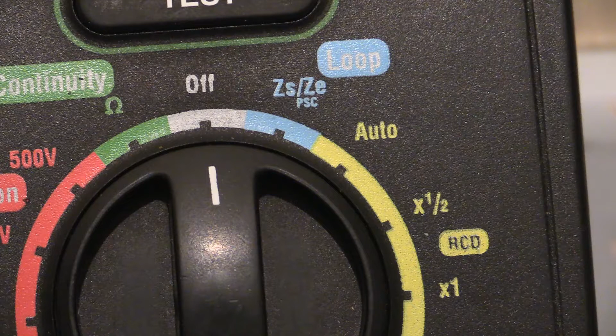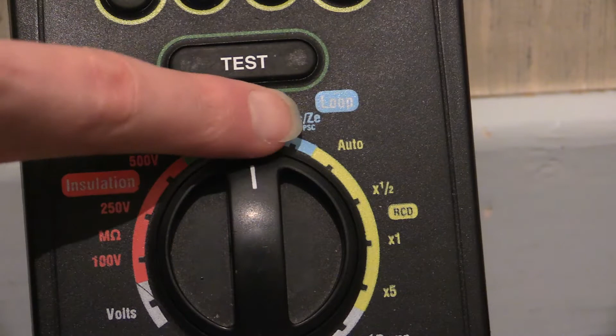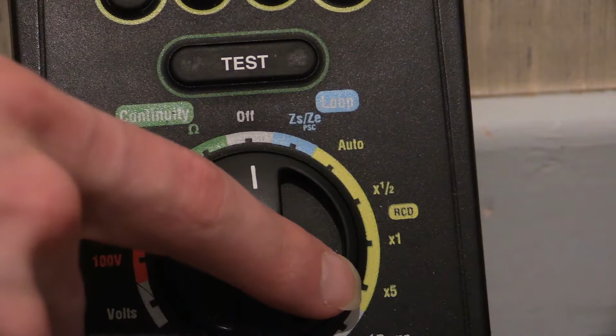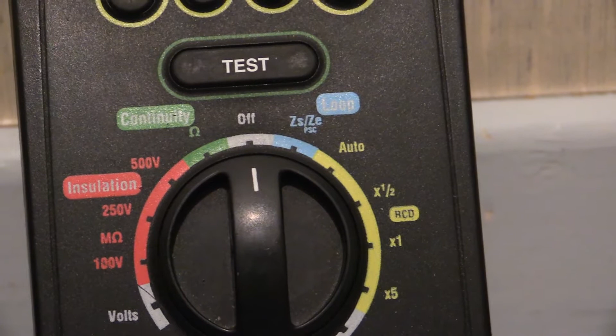Moving down then, you've got that big long yellow section, and just down there it says RCD. With this you've got a variety of options to test out an RCD. You've got auto up the top. If you turn this dial around so that it's on the auto function, it'll carry out a variety of tests. You just push the test button and it'll whiz through the tests and do them all automatically for you. Or if you want to pick a particular test, you can do half current, 1 current, or times 5 current.